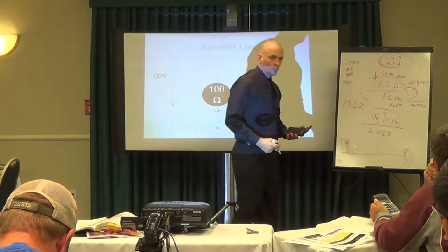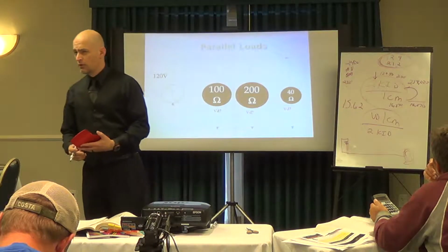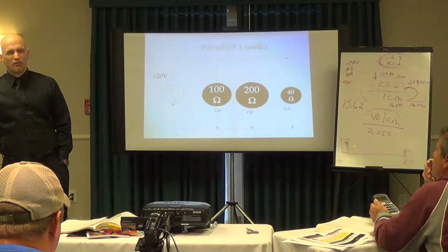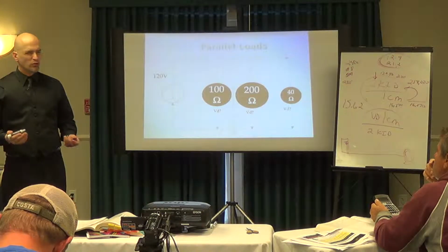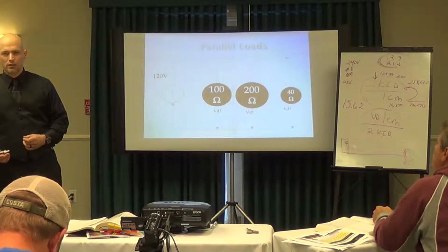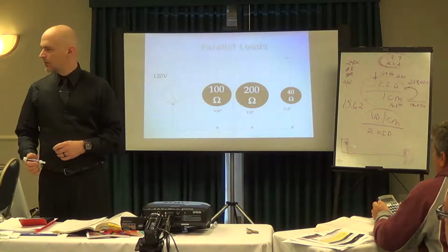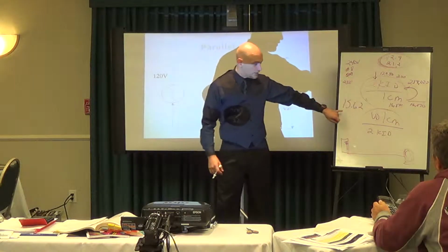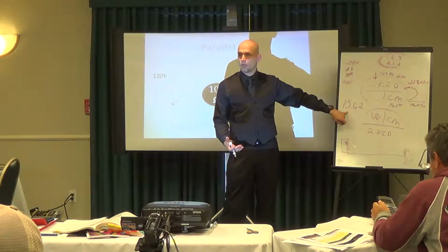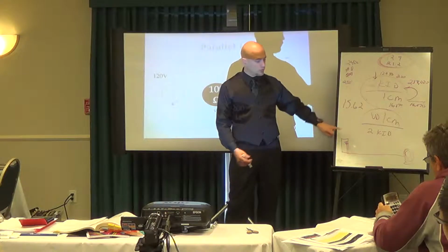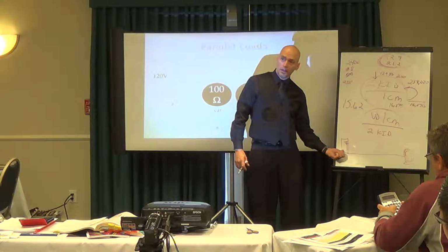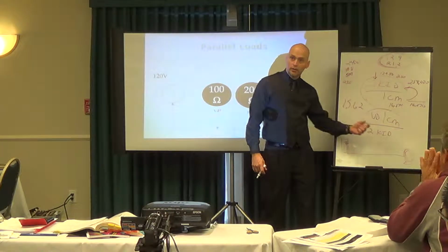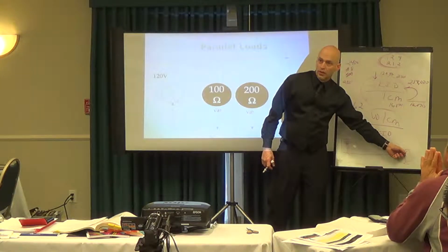And what is that number? Did I lose 15%? Is that what that means? Because we talked about voltage drop in percentage, right? Usually we're talking about voltage drop not more than 5% or not more than 3%, or 6.5, is that what it is? So what this is right here, guys, is the volts. It's the physical number of volts that you representatively lose in that distance. So if you put a meter here at 240 volts, down here you'd have 240 minus whatever this is at the actual load location.